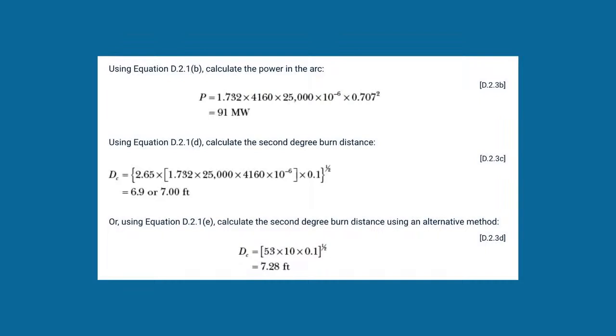Temporary. Well, the reason I was asking is that 7.25 feet is pretty far. I mean, that's a massive event. We call that an unintended rapid disassembly in the field when you're involved in these arc flash events. And you know, 7 foot, that's far. And these are calculations that have been done by IEEE and labs where they've actually done the testing and figured out these calculations in order to determine what these distances are going to be. Gotcha. Okay.